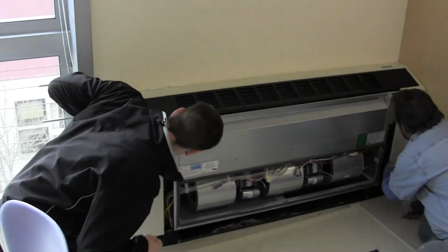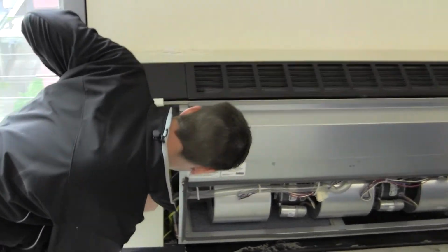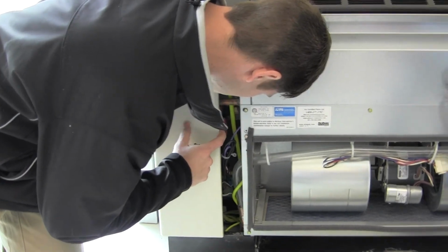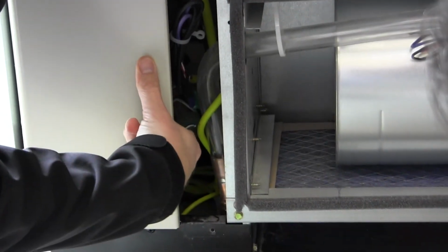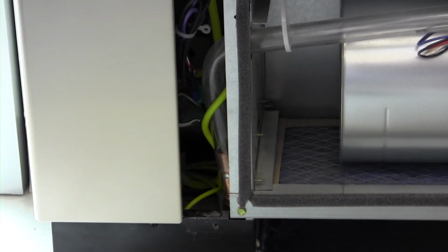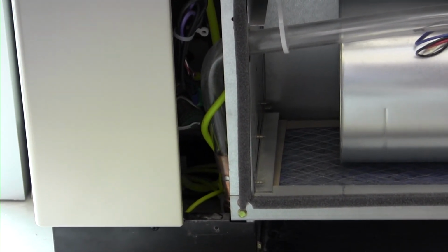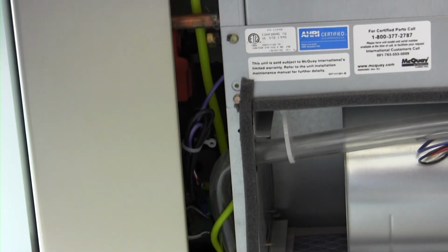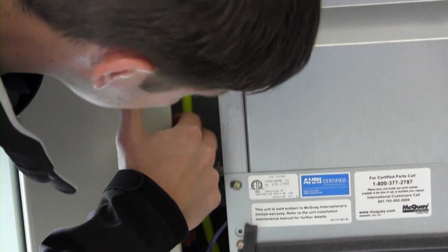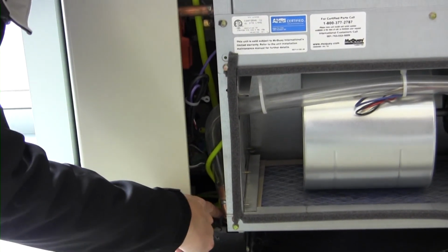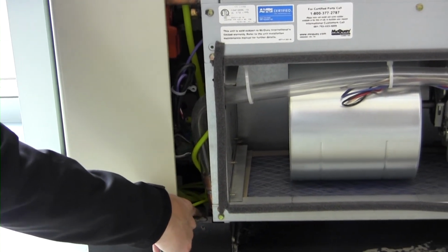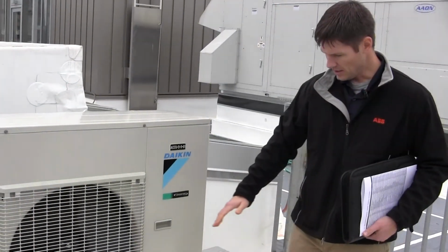What else we got? We have control valves over here with the Belimo actuator. We got balancing valves. Looks like a strainer with a hose bib connection and a blowdown valve. And this is your condensate drain. This condensate drains down into a similar one like the last one, where it's got a reservoir. It'll fill up and then it pumps it up through here and out. It's on. All right.